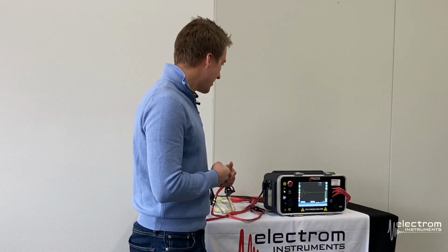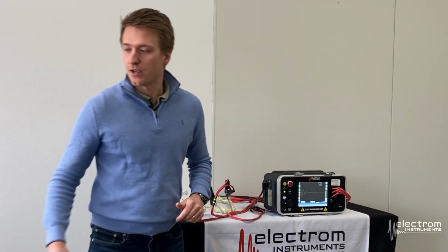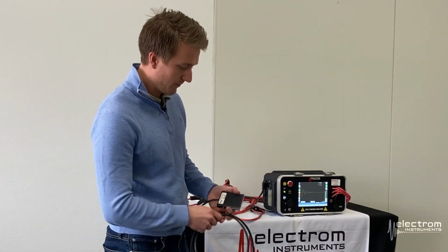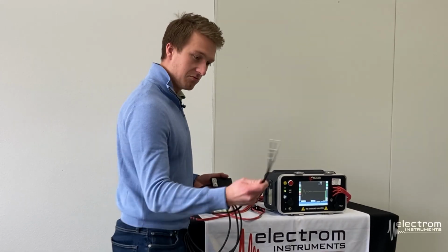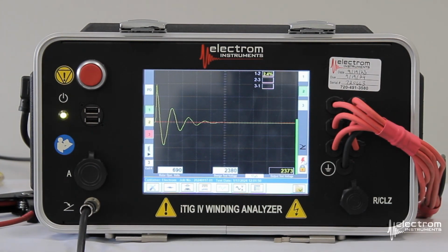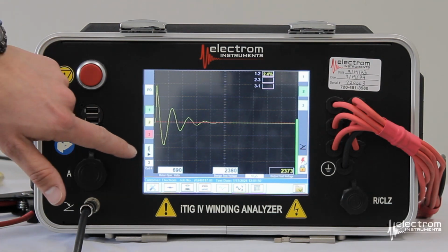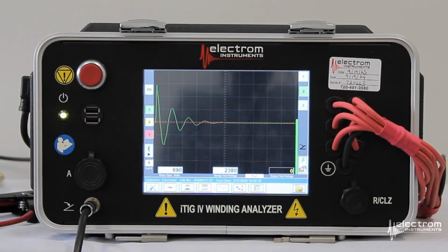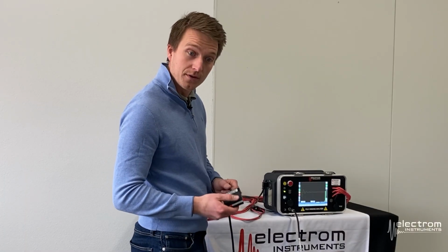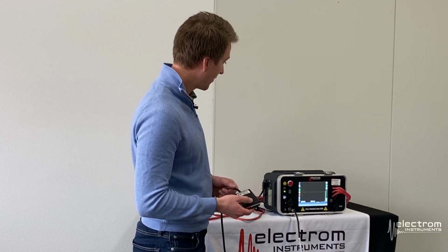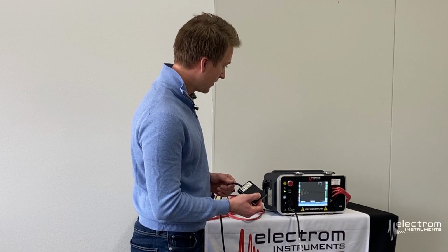One way to speed up and make this an even more efficient test process is to use a foot pedal. So you connect the foot pedal to the foot switch jack, and then you see the foot switch icon show up near the bottom right. We now click the next coil button, arm the instrument, and then you step and hold, or press and hold the foot switch to run the test. So press and hold, runs the test.